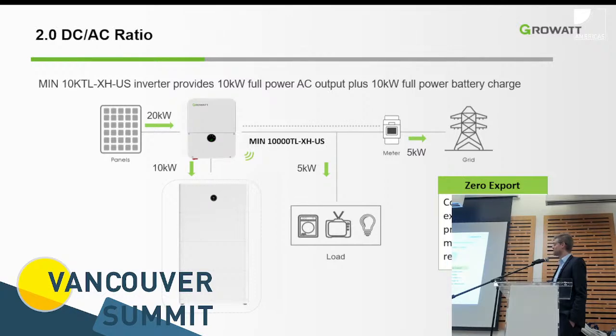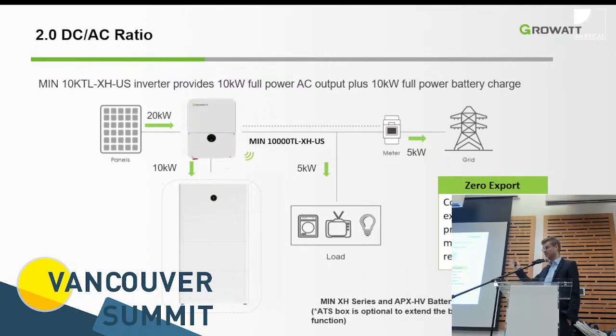There are multiple modes the system can be programmed to. In a zero export mode, you would just control that the meter detects, oh, I would be feeding in right now, but I don't want to feed in because of zero export. Then the inverter will just be throttled to not output more on the AC side than the load is currently needing.